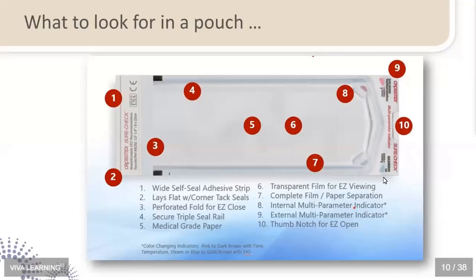Most pouches are going to be a type 1 chemical indicator, which is only going to register one of the critical parameters of sterilization, which would be, in this case, time, temperature, and pressure in the form of steam. Some pouches are multi-parameter, which means they're going to react to 2 or more of the sterilization parameters, so you're going to have a more sophisticated evaluation of the sterilization process.